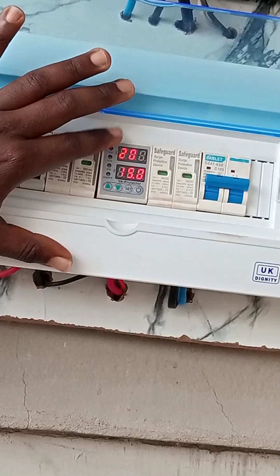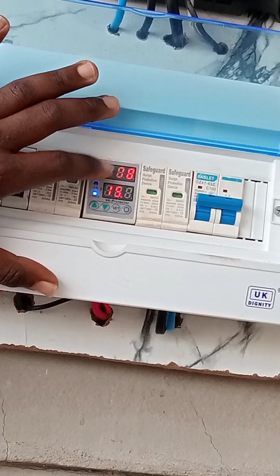So currently, the NEPA, that is the normal electricity coming in, we use a protective device so that the moment the voltage is below 160, it's cut out from the inverter. And we also protected the amps so that there will not be overload. We have 2 breakers here.